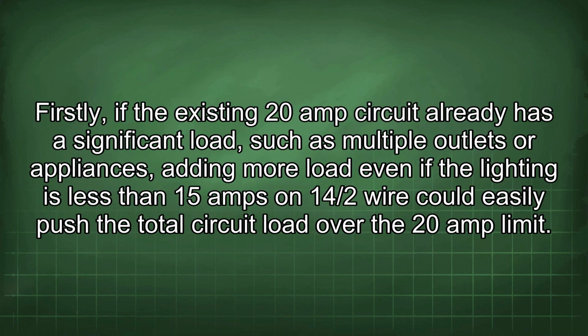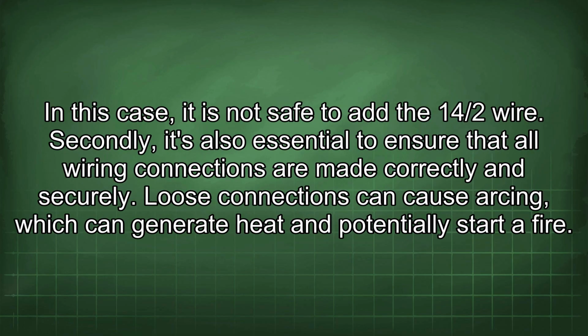Firstly, if the existing 20 amp circuit already has a significant load, such as multiple outlets or appliances, adding more load, even if the lighting is less than 15 amps on 14/2 wire, could easily push the total circuit load over the 20 amp limit. In this case, it is not safe to add the 14/2 wire.